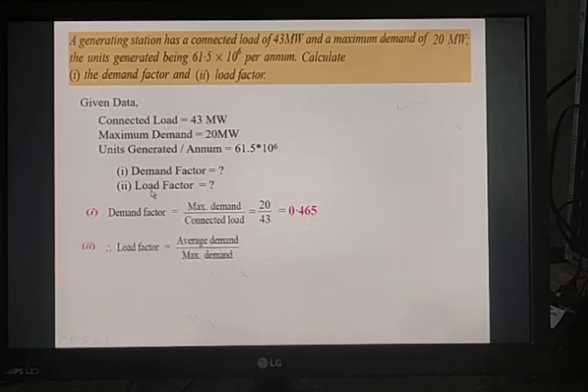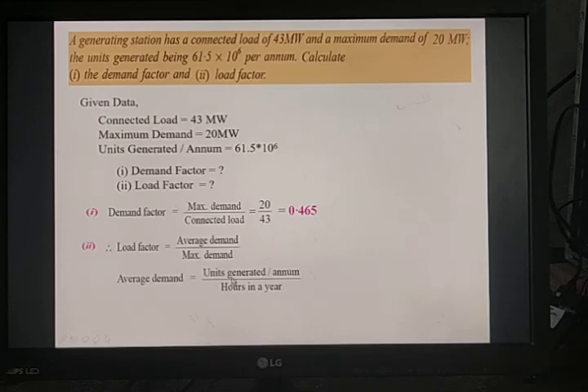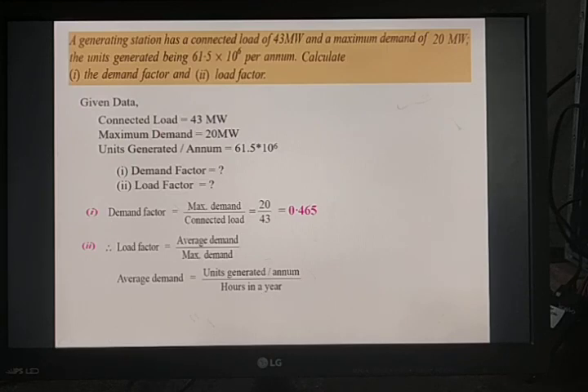The second parameter is the load factor, defined as the ratio of average load to maximum demand. The maximum demand is 20 megawatt, but the average load is not given. We calculate: average load = units generated per annum / hours in a year = 61.5 × 10⁶ / 8,760 (365 days × 24 hours).